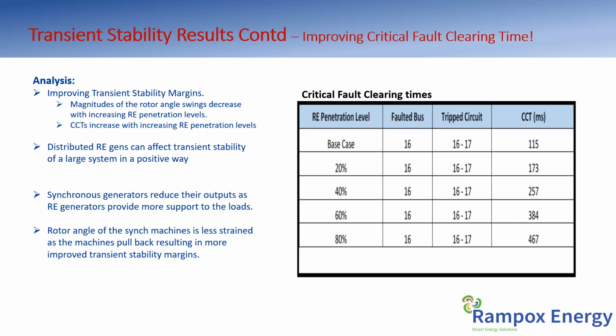If you're running away from that, you say if a fault happens I can tolerate up to 460, that means you are super good in terms of stability margins. That's what this measure says. But if it goes beyond your 100 milliseconds, say 80 or 90 milliseconds, that means you're seeing problems, because even your breakers may not be able to save you when that disturbance happens. They won't be quick enough, and that means you'll have lost your generators or your system. That's normally how the planning is done.